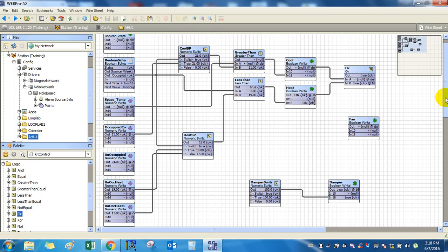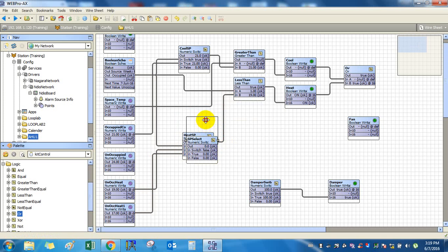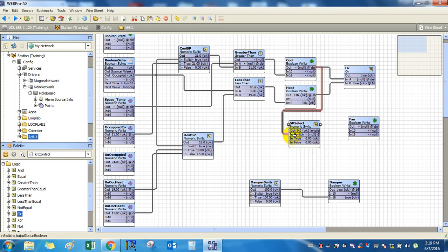Now we have two set points, cooling set point and heating set point, but for graphics we need to calculate the effective set point. So for that, add a numeric switch. I have a numeric switch on my wire sheet. I will just duplicate this and name this as set point select, SP select. So whenever there is cooling in your space, that time you have to pass your cooling set point, else you have to pass your heating set point.